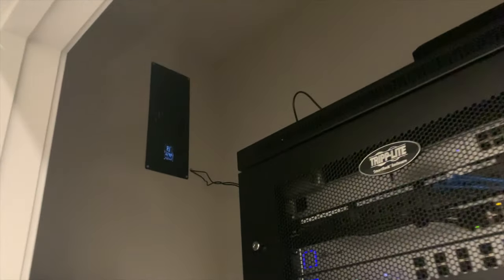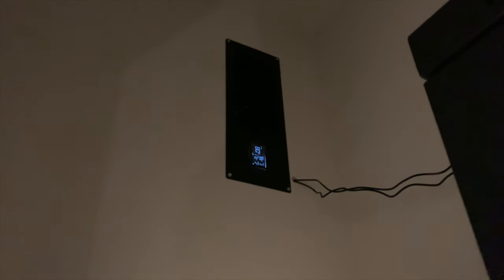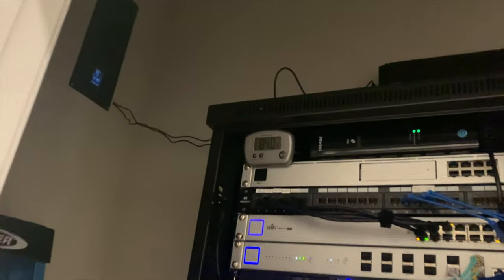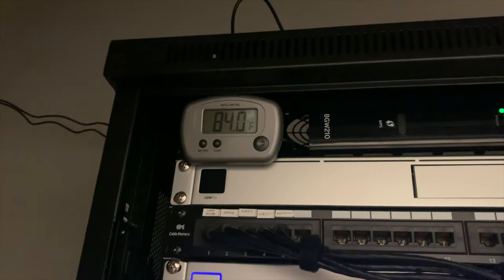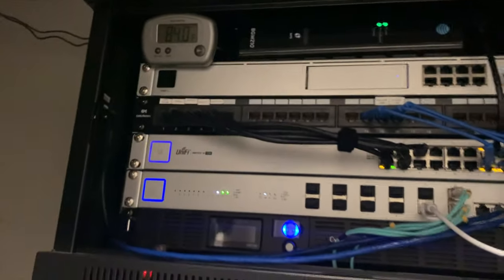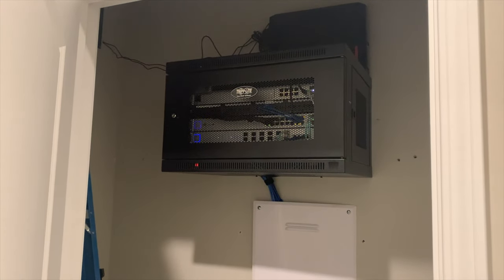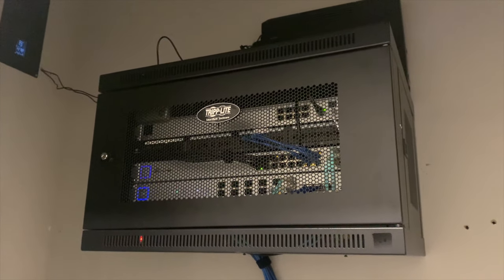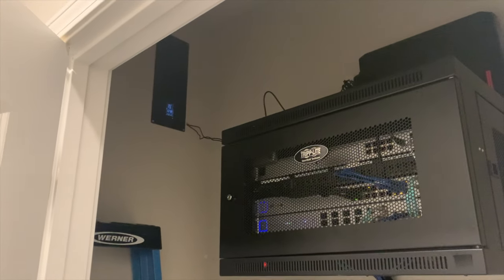Got that reassembled pretty easily. I'm not going to take the fans out — there's really no need. You can trust me when I say they are definitely swappable if you so choose. It's been a few hours since we installed the exhaust vent, and it looks like we're sitting at 80 degrees Fahrenheit as opposed to the normal 90 to 91. The other temperature probe says 84 degrees Fahrenheit — they are in two different places inside the closet. But from a subjective point of view, it feels significantly cooler already when you open the door.